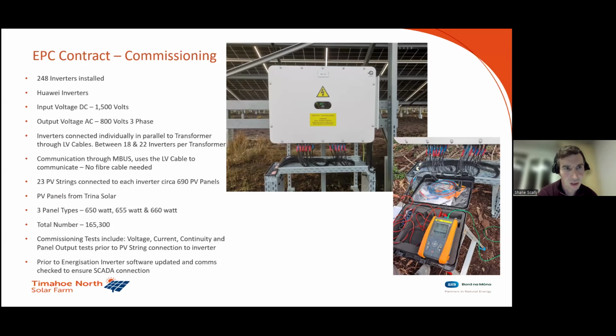There's a question there about ducting and items like that - the LV cables themselves we direct bury, while the MV cables between transformers are ducted. Each inverter, there's about between 18 and 22 inverters per transformer, slightly different depending on the design of the individual areas. The communication is quite interesting from my point of view - the inverters aren't connected with a fiber cable, they actually communicate to the transformer center through M-bus, which essentially uses the low voltage cable to communicate. It took me a while to get around it - I am a civil engineer, so bear with me on that one.